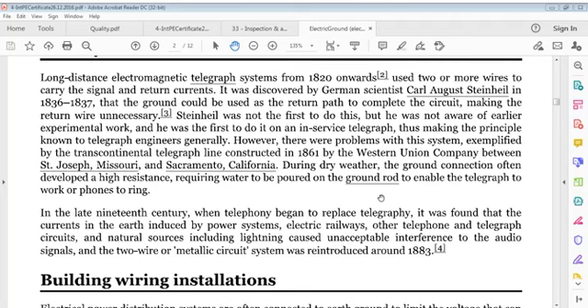However, there were problems with this system, exemplified by the transcontinental telegraph line constructed in 1861 by the Western Union Company between St. Joseph, Missouri and Sacramento, California. During dry weather, the ground connection often developed a high resistance, requiring water to be poured on the ground rod to enable the telegraph to work or phones to ring.